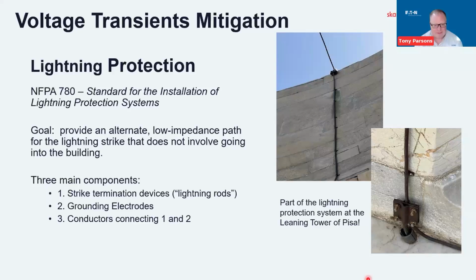There are three main components. We have the strike termination devices, AKA the lightning rods. We have the grounding electrodes to connect to the actual conductive earth, and then conductors that connect number one to number two. Simple if you look at it in that way. And again, you see these things everywhere.